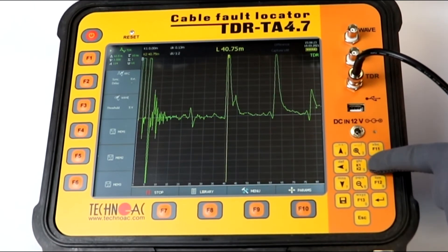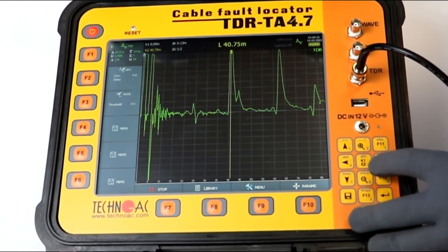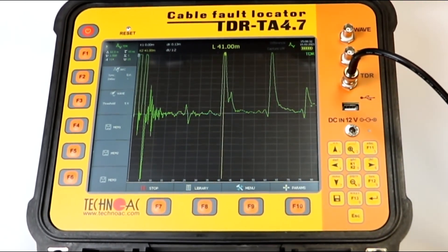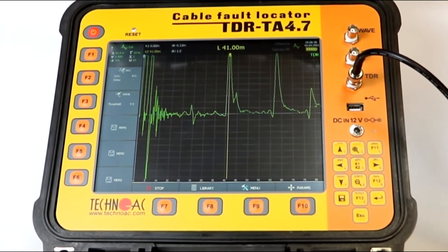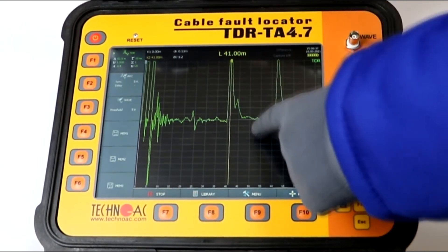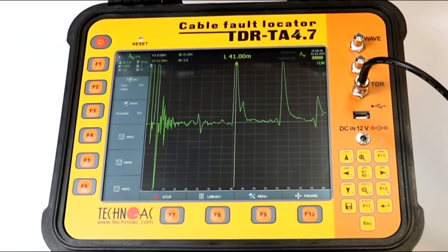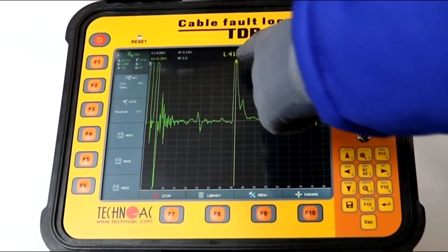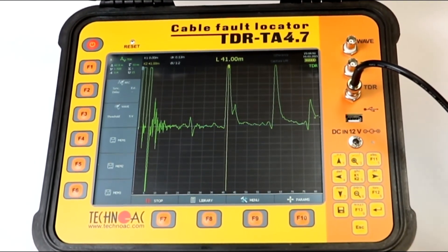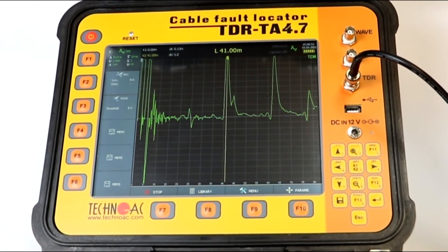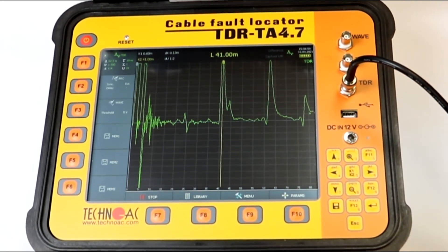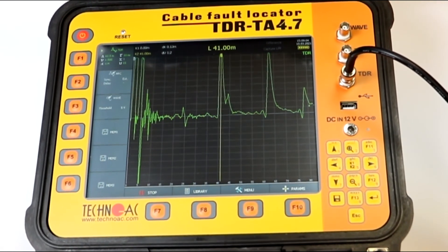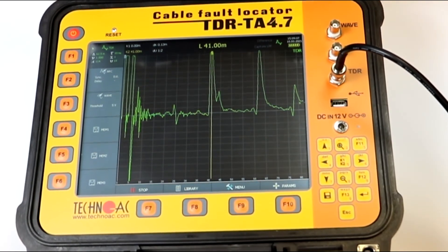By pressing the K1/K2 button, we can switch to Cursor 2 and adjust the position of the cursor to specify the spot where we have the damage. This particular part of the graph indicates that we have located a breakage of the cable. The cable is split open at 41 meters, meaning that if we go 41 meters alongside the cable, we will be able to spot this fault. Note that the accuracy of this device is 12.5 centimeters.